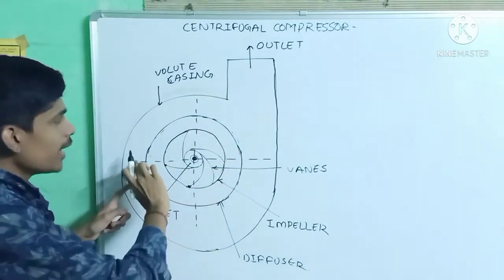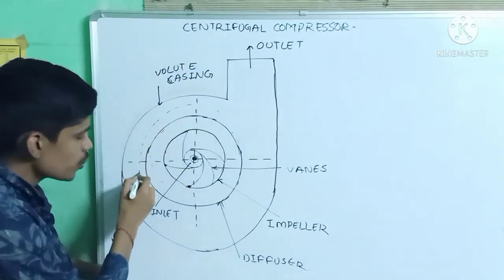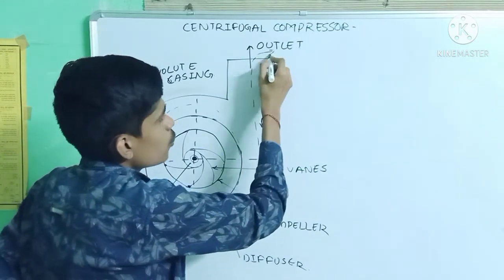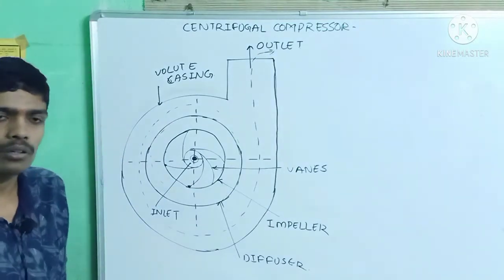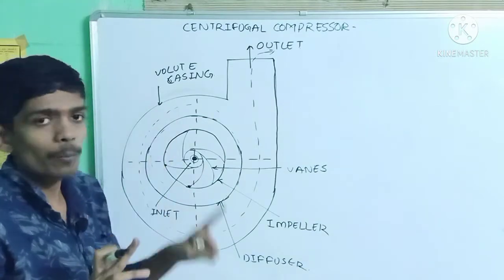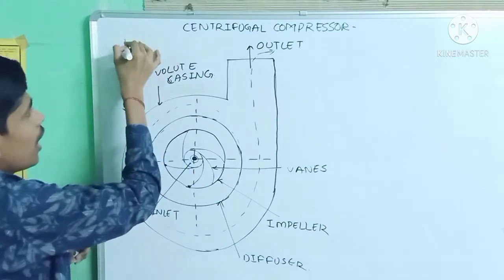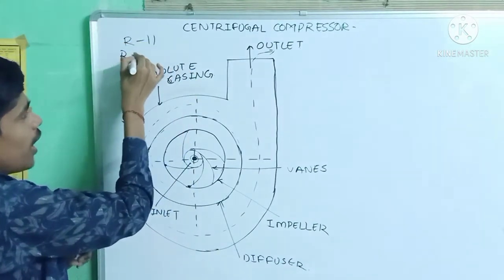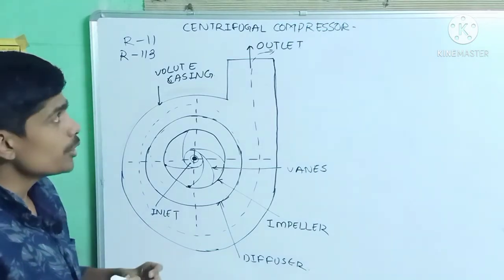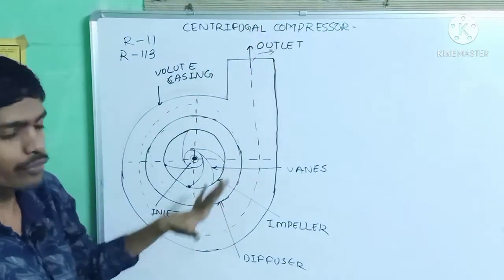As the refrigerant passes through the volute casing, kinetic energy is further converted into pressure energy, and finally it is discharged through the outlet. For centrifugal compressors, refrigerants with high displacement, large displacement, and low condensing pressure should be used — such as R11 and R113.